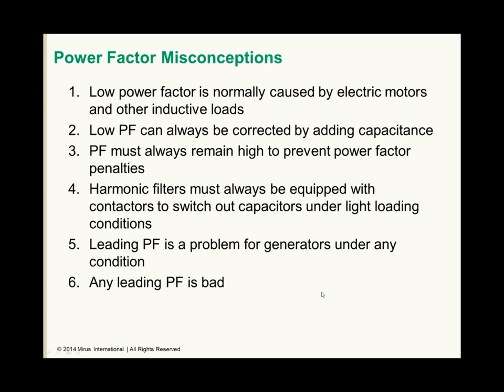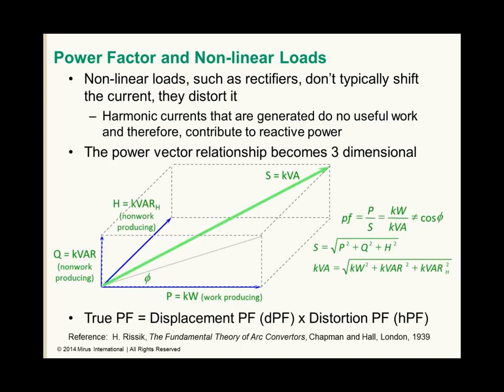So when we consider power factor with nonlinear loads that are introducing harmonics in the power system, these would be loads such as 6-pulse rectifiers and other thyristor type bridges and conversion, basically power electronics that converts AC to DC. These rectifiers don't typically shift the current, but they distort it. So harmonic currents that are generated do no useful work and therefore contribute to reactive power.